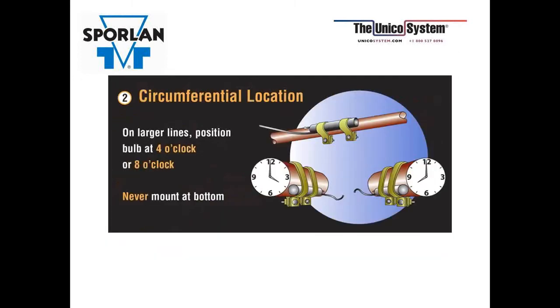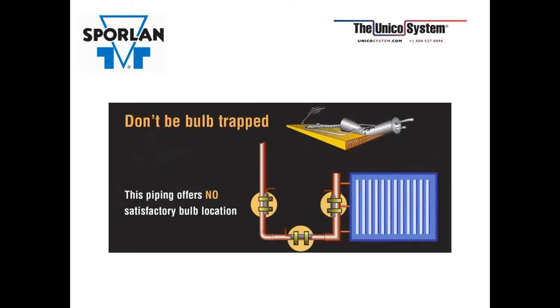So where it's located in the circumference. On the larger lines, typically 7/8 or larger, we want it at the 4 o'clock position or the 8 o'clock position. You don't want to mount it at the bottom because that's where the oil return is coming back. Oil acts as an insulation, and you're not going to get a good temperature reading through your bulb. And you also don't want to be bulb trapped.